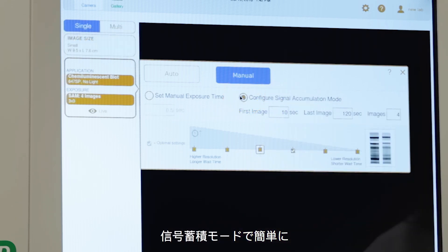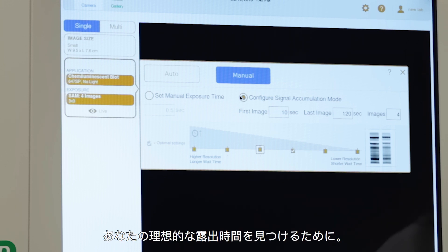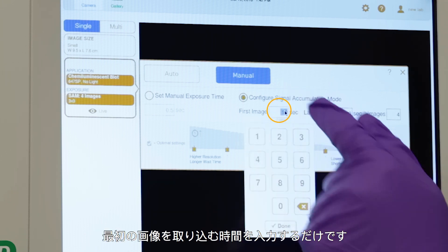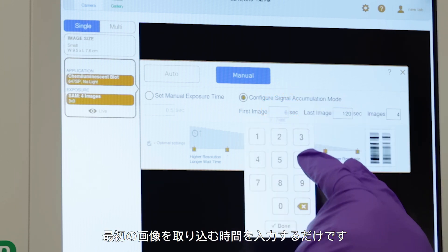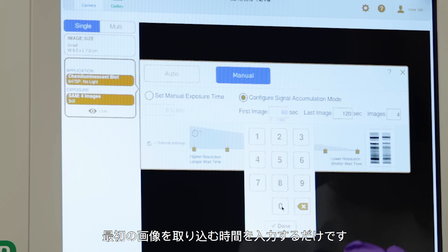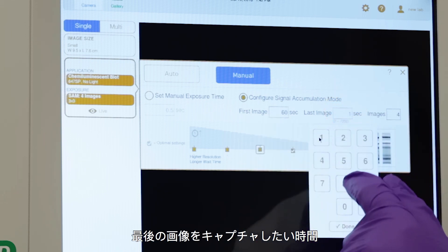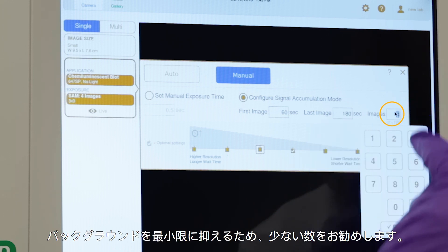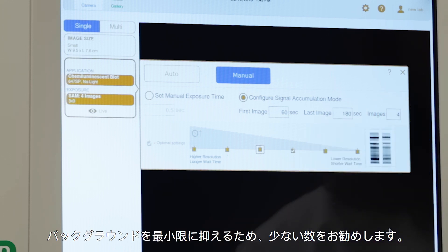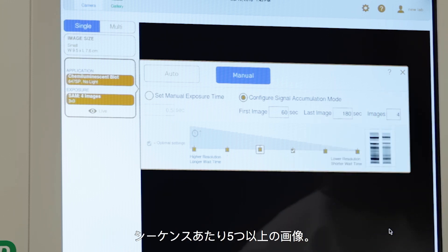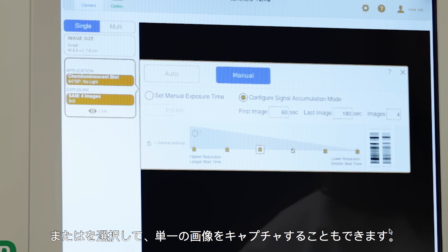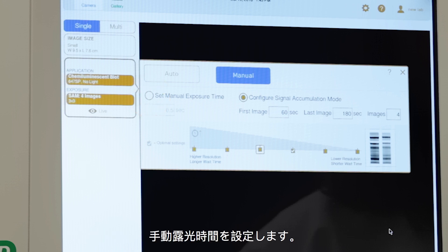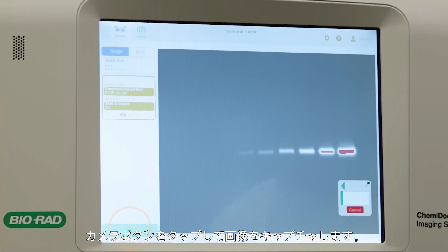Signal accumulation mode makes it easy to find your ideal exposure time. Simply enter the time you want your first image captured, the time you want your last image captured, and the number of images you wish to view. For minimal background, we recommend fewer than five images per sequence. Or you can simply capture a single image by selecting set manual exposure time. Tap the camera button to capture the image.